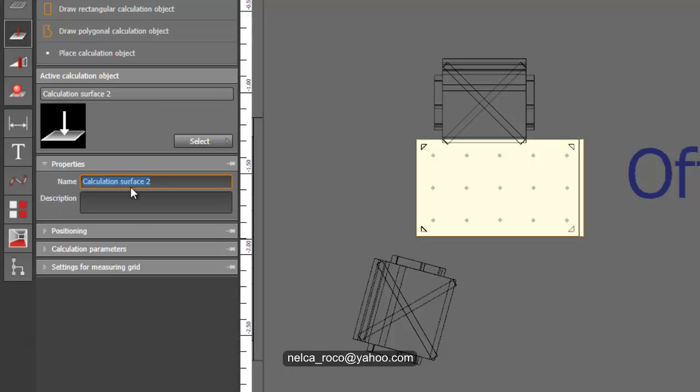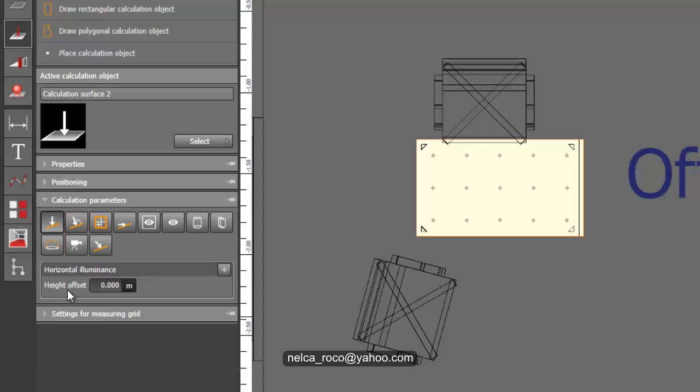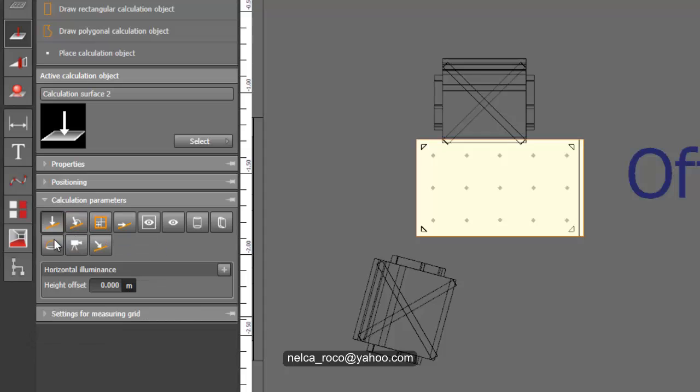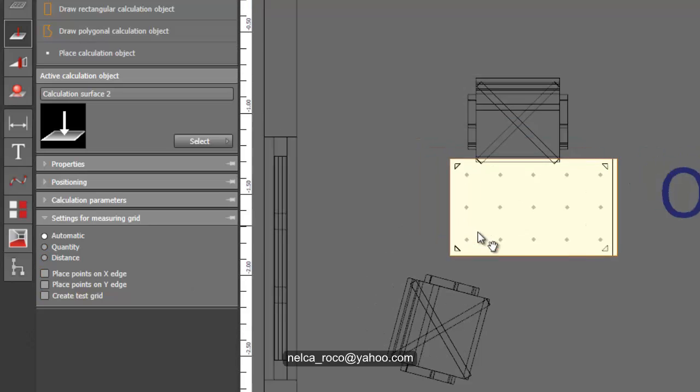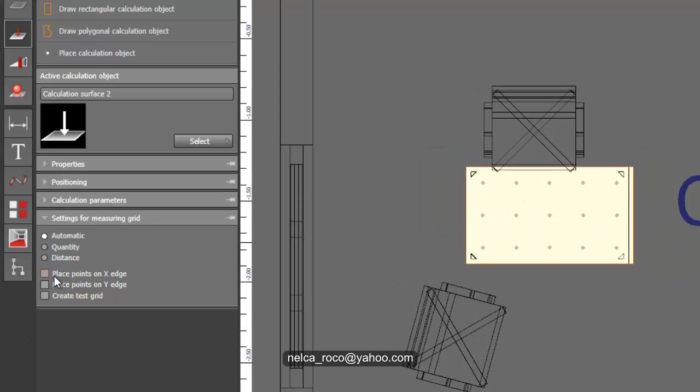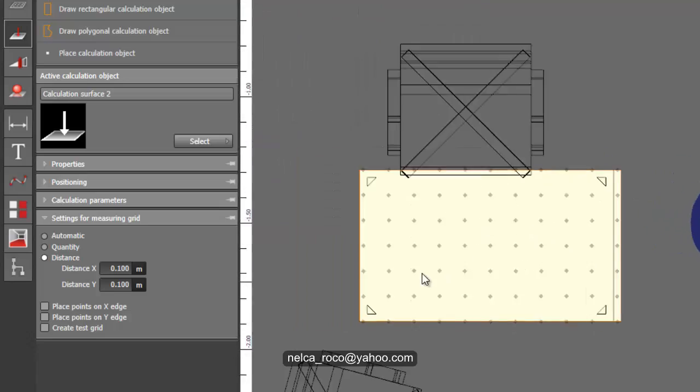You can create another calculation surface on this table. I can say this is calculation surface for office. The positioning will be, since most office tables are 0.76 meters height, you can make it 0.76 to be precise. The calculation parameters, you can select horizontal or perpendicular. You can also edit the points here, for example, distance of the points would be 0.1 by 0.1, and the points are now getting closer to each other.